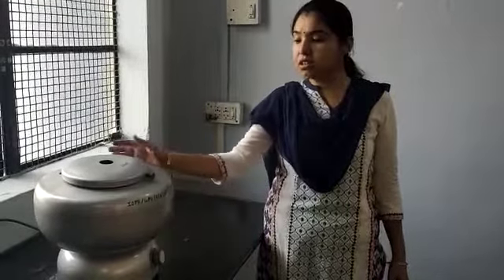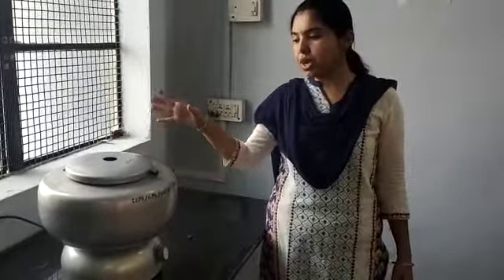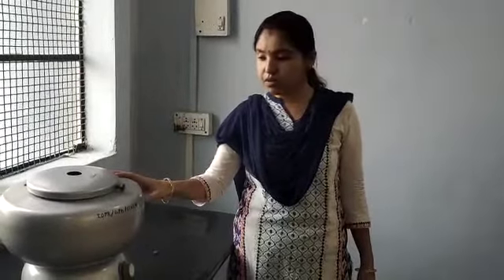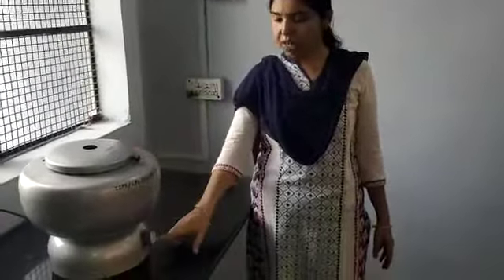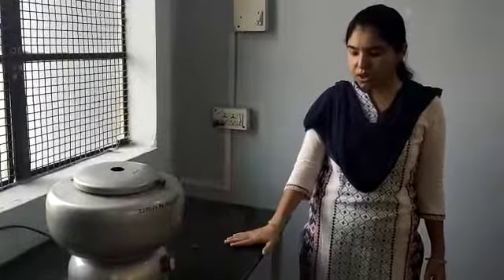So it is provided with the temperature control also, and here the centrifuge chamber is also refrigerated and is kept at high vacuum. The one that we are going to use today for our practical is the low speed centrifuge, which has a maximum speed of 3500 rpm. Now we have switched on the equipment. So first we will load our samples.